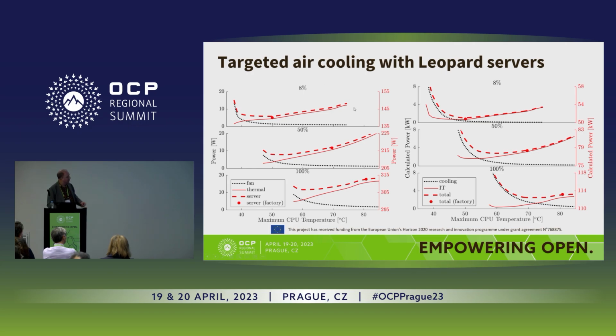So where the red curve drops, that's the temperature that you should really operate your data center. But the sweet spot moves as the workload changes. So if we had some way of controlling the BIOS so that we could change the temperature of operation of the CPU, so you're always at the sweet spot, then that's what the BIOS should be doing. The red dot on there is actually what is done by the BIOS if we didn't take control of the fan.